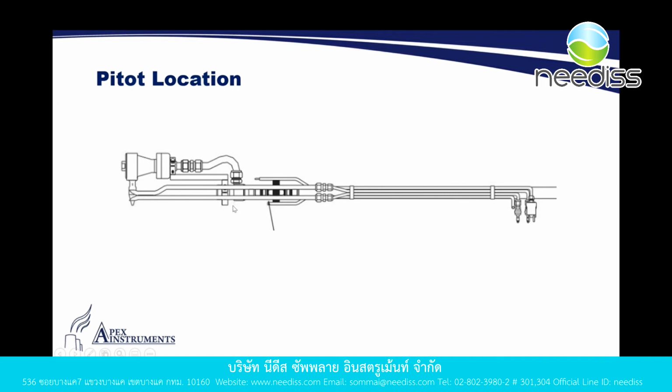So it would actually be back here somewhere. So we have various pitot lengths that accompany each of the different options that you have for method 201A to exactly match the length of the cyclone. So your nozzle and your probe are in alignment as required by the method.